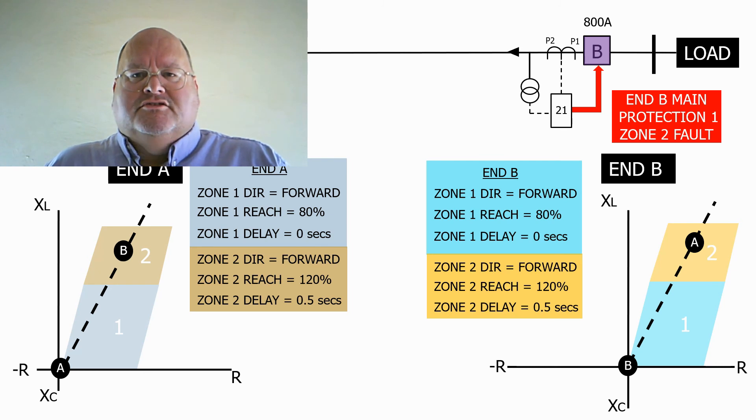The decision on whether or not to use this type of configuration depends on the required fault clearance time of the network. If a half a second delay is OK, then the scheme can be used. If the delay will start causing issues with network stability or other voltage issues, then a more complex scheme will be required, involving communication between the two feeder ends. This is covered in the next lecture.